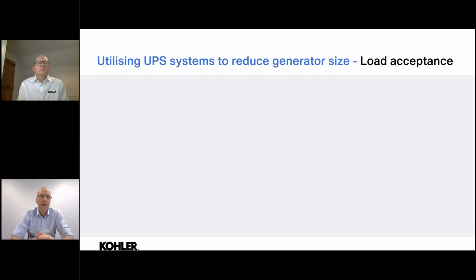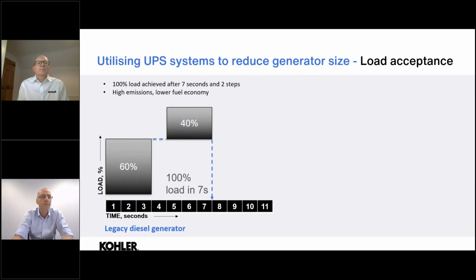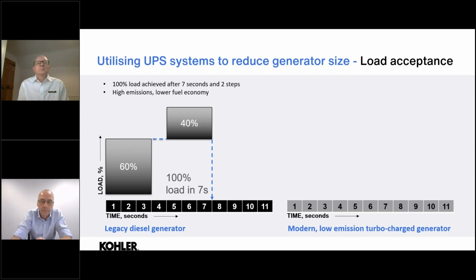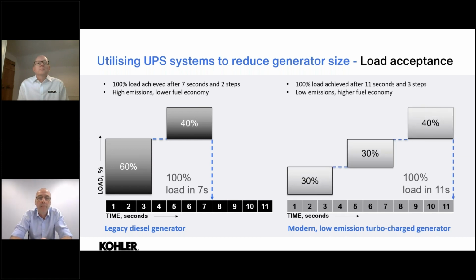So one of the big things that we look at in keeping everything right sized is utilizing the UPS systems to reduce the generator size. This is around the load acceptance. So typically with a legacy diesel generator, you would have a load step of 50–60%, followed by the final parts of the load to the 100% in around 7 seconds. The old legacy diesel generators are sort of high emissions and low fuel economy, but we're able to give those big load steps.